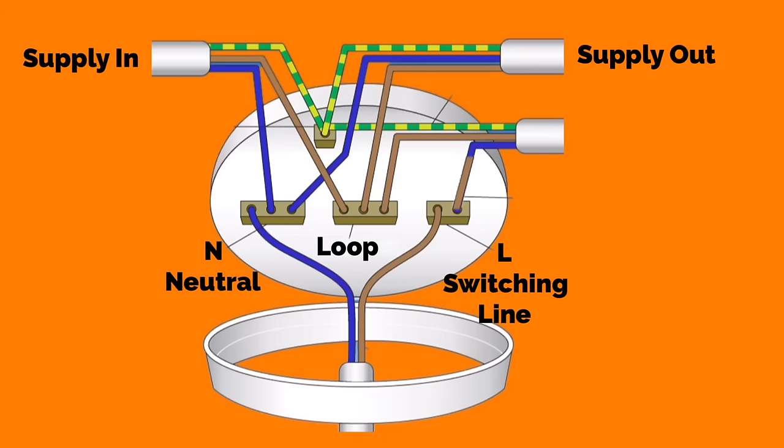If the supply comes in on the left hand side, it will bring in a permanent neutral connection, which is terminated within the neutral block. It will bring in a permanently connected line conductor, which is connected into the loop terminal in the centre, and bring in a circuit protective conductor terminated into the earth connection within the ceiling rose itself.